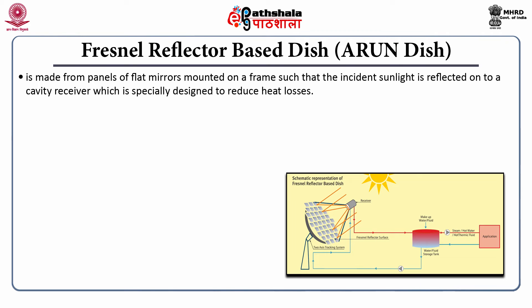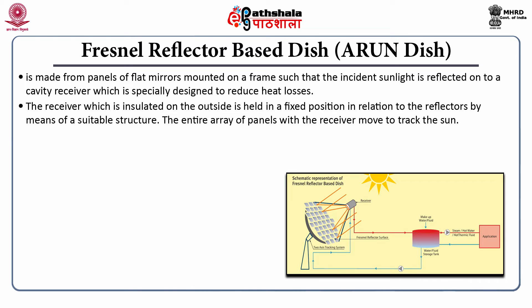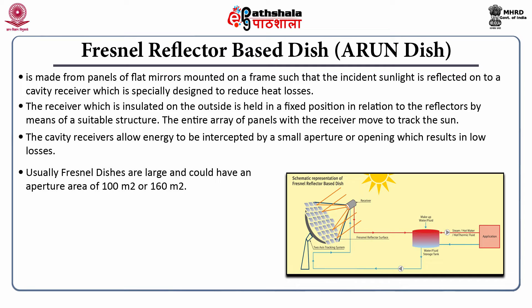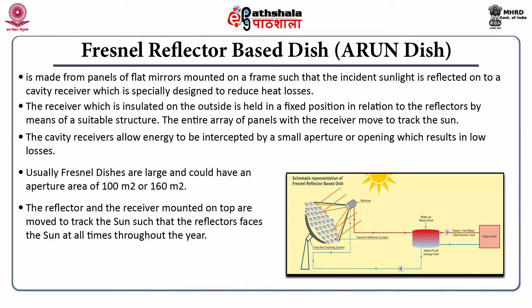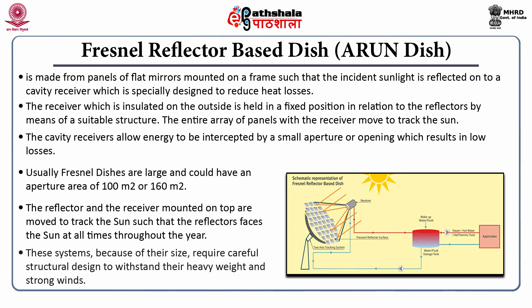The Fresnel reflector-based dish — the Arun dish — is made from panels of flat mirrors mounted on a frame reflecting incident sunlight onto a cavity receiver specially designed to reduce heat losses. The receiver is insulated on the outside and held in a fixed position relative to the reflectors. The entire panel array with receiver moves to track the sun. These Fresnel dishes are large, with an aperture area of 100 to 160 m², and require careful structural design to withstand heavy weight and strong winds.